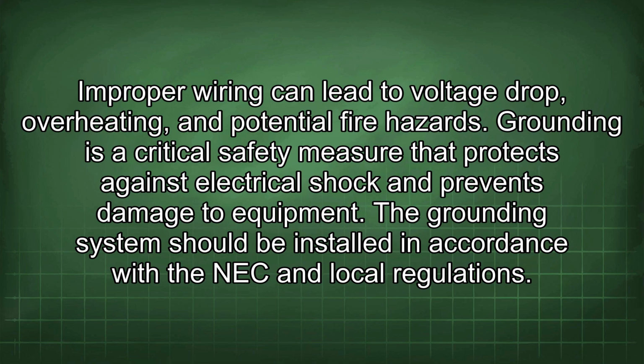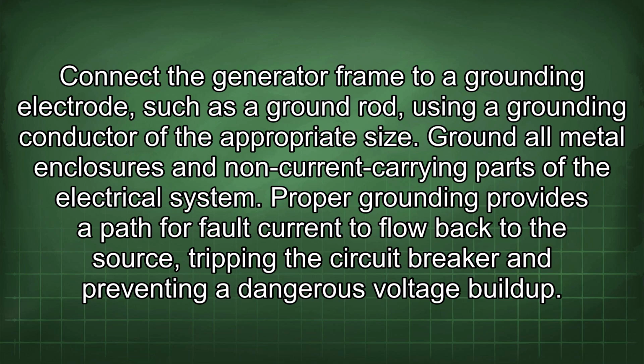Grounding is a critical safety measure that protects against electrical shock and prevents damage to equipment. The grounding system should be installed in accordance with the NEC and local regulations. Connect the generator frame to a grounding electrode, such as a ground rod, using a grounding conductor of the appropriate size. Ground all metal enclosures and non-current carrying parts of the electrical system.